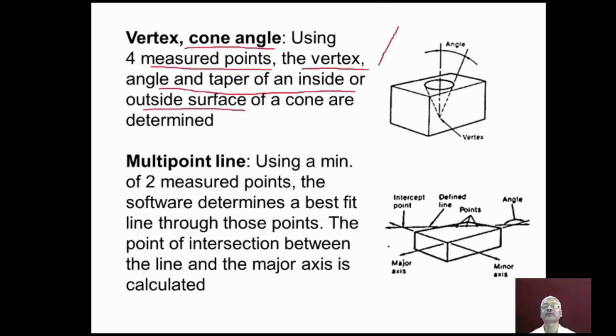So if you have an extended outside cone, 4 measuring points should be given, and software can calculate the coordinates of this vertex, and this angle, and then the taper that can be calculated. Multi-point line using a minimum of 2 measured points, the software determines the best fit line through the selected points. The point of intersection between the line and the major axis can also be calculated. We have this major axis here, and we have the best fit line here. So these are the 2 measured points, and this is the best fit line. And the angle between the major axis and the best fit line can be calculated using the software.